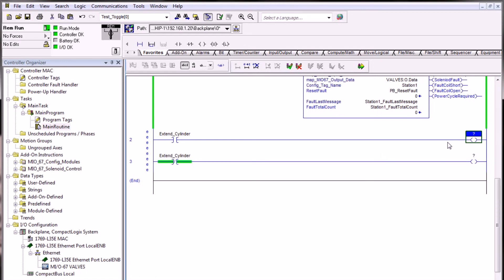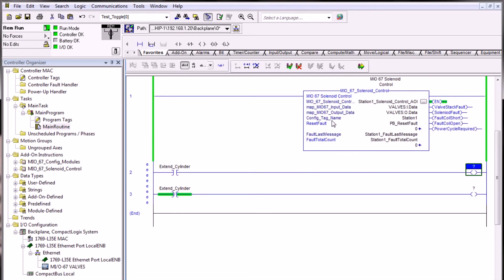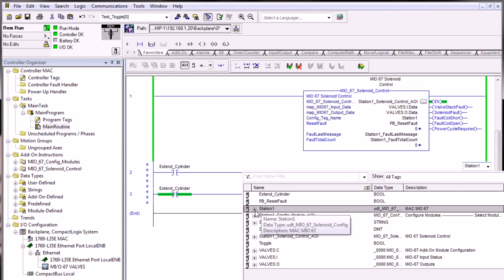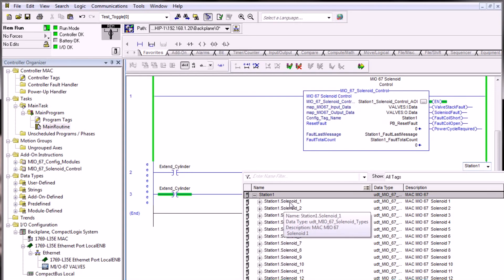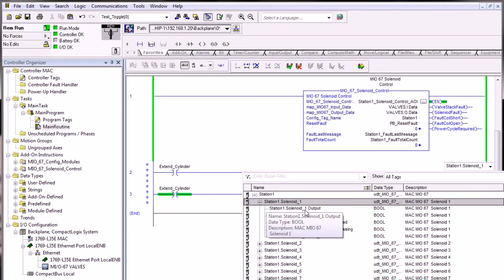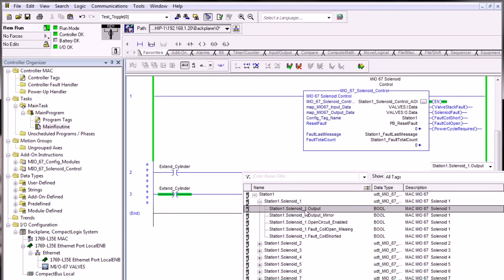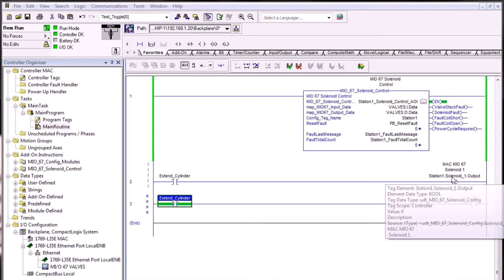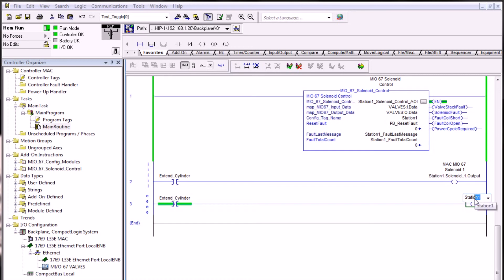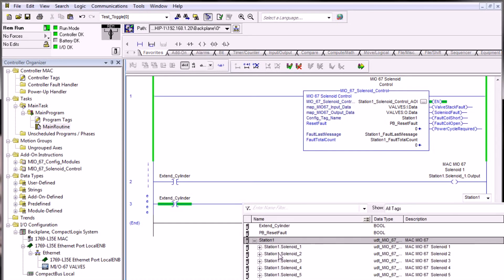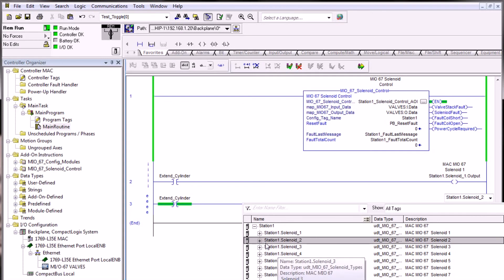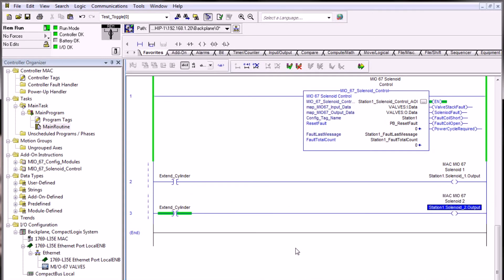In order to reference the station one solenoid control, we're going to use the config tag name that we created, station one. We can begin to type station one in the output coil here and then use the arrow to select and expand the tag name. Here we can select solenoid one and expand the dot o output instruction. This will give us access to control the output of solenoid one. We can then do the same thing by referencing solenoid two here by beginning to type station one and expanding the tag name to solenoid two and then selecting a dot o for output.